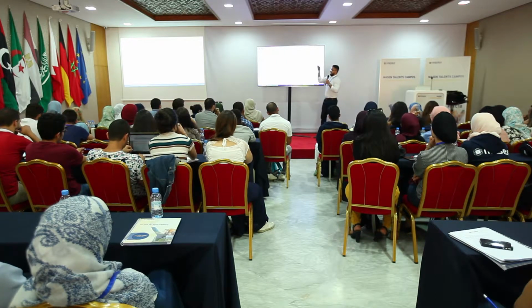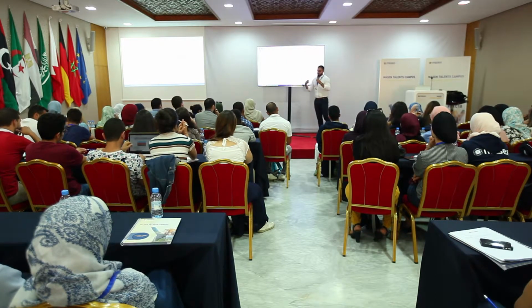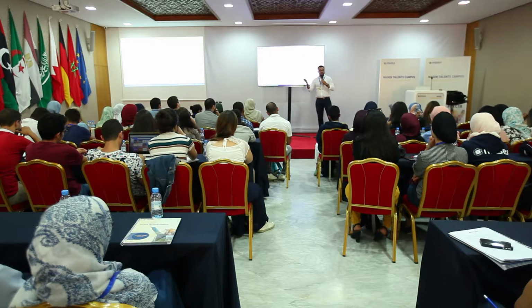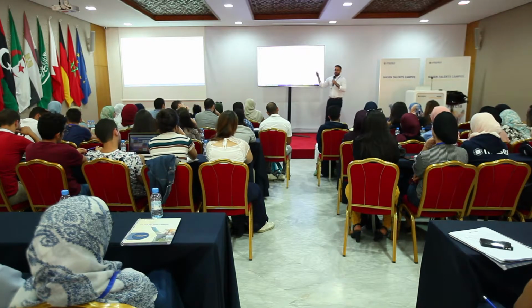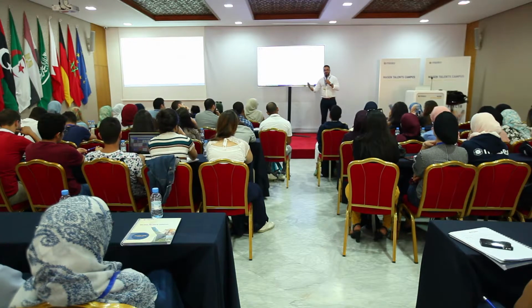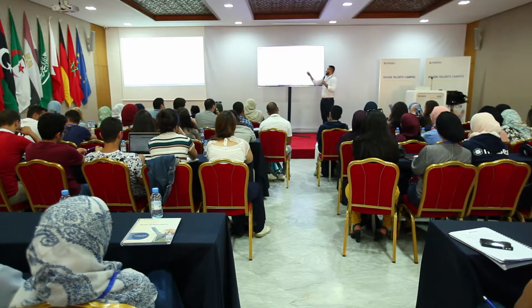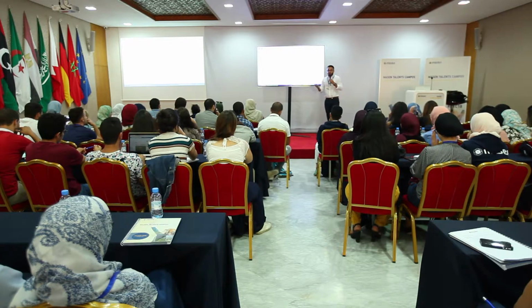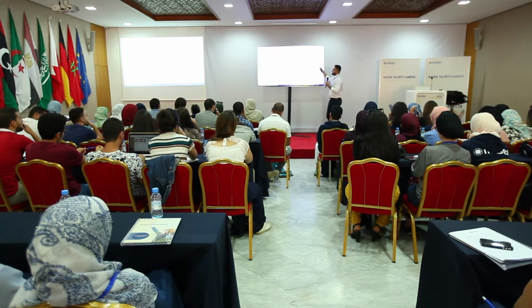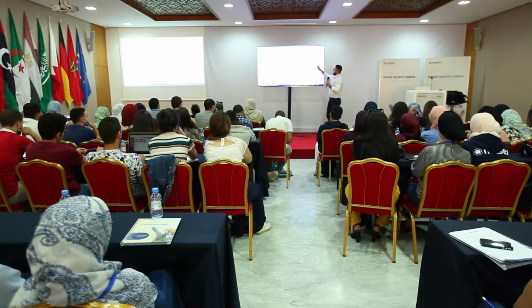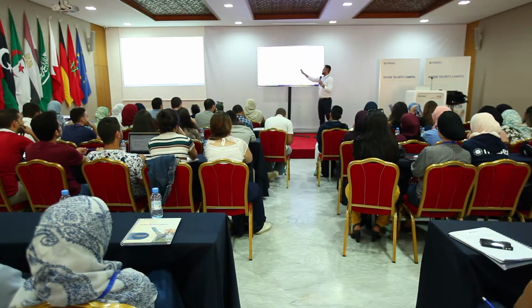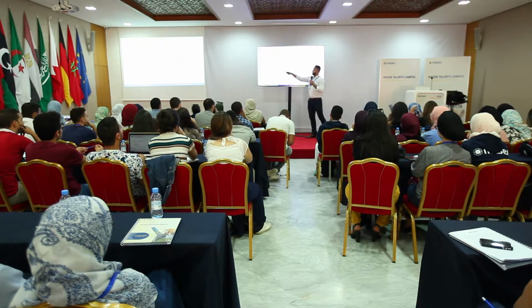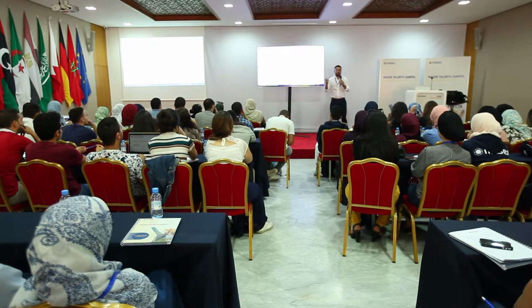So if I want a 100 megawatt electric plant, and this is the design condition, this is how large the field should be. This is basically what it is. But that is only true at that point. So in solar systems, in renewable systems, a design that is only at design point is useless, because the design point is only met once a year. Most likely, unless you have a lot of storage and you can control that, these conditions will never be met again.